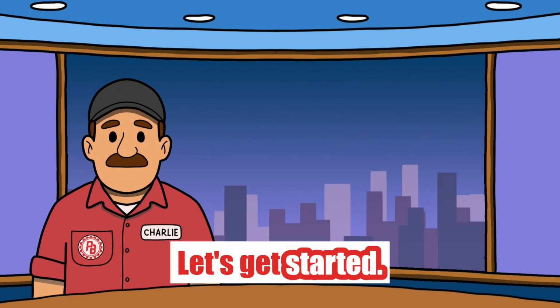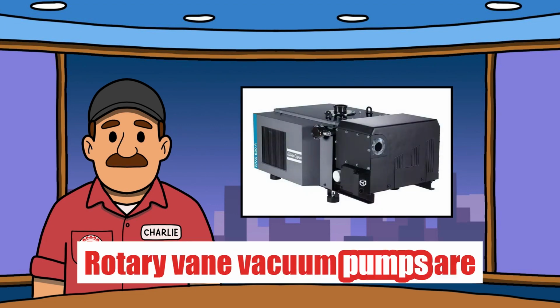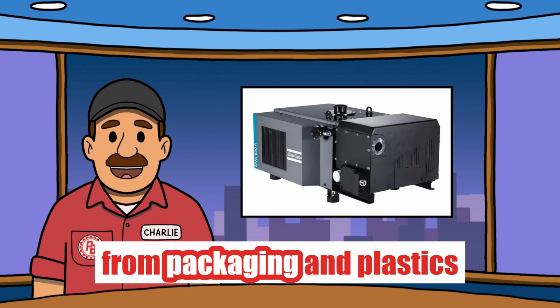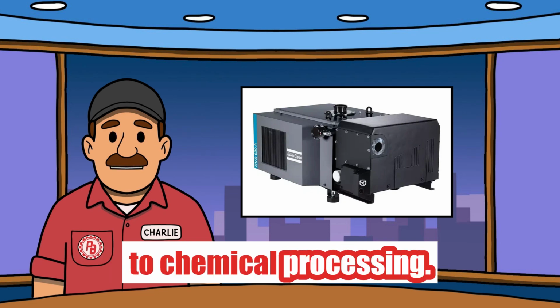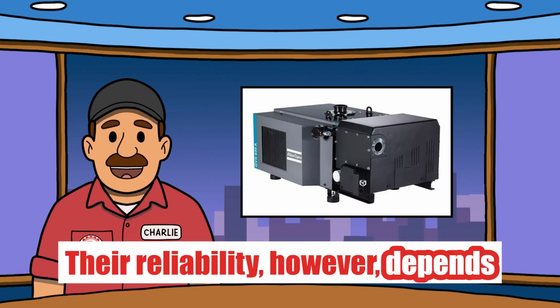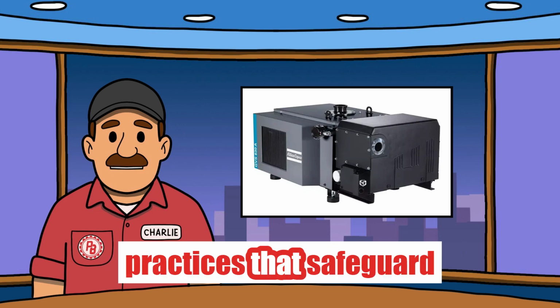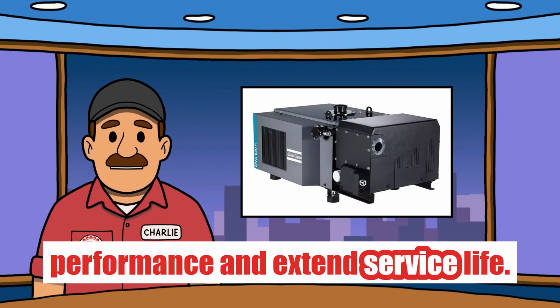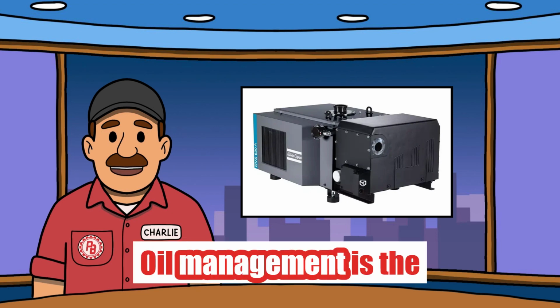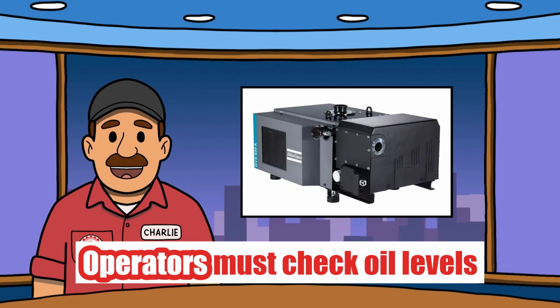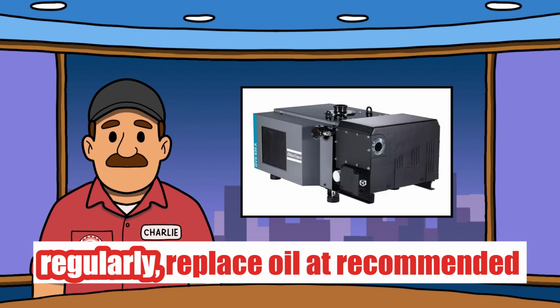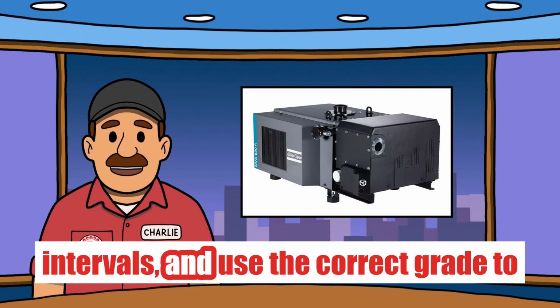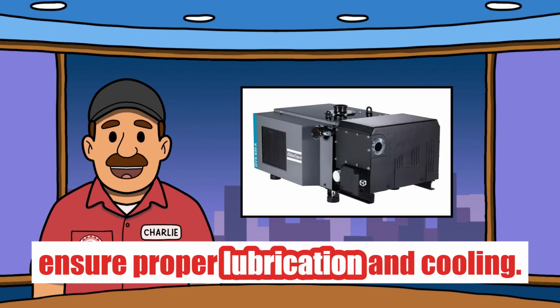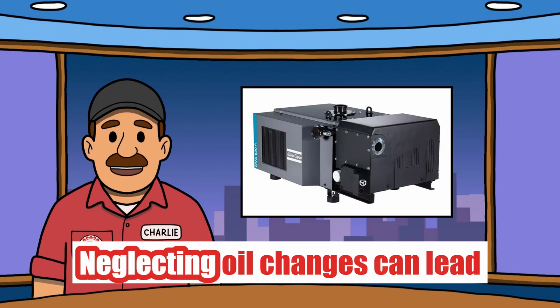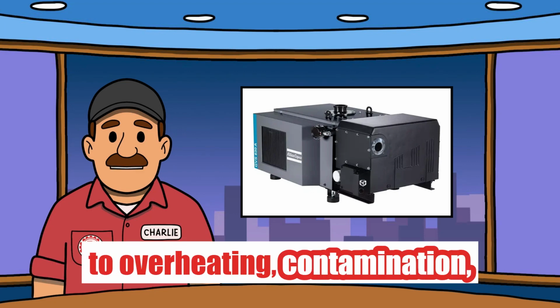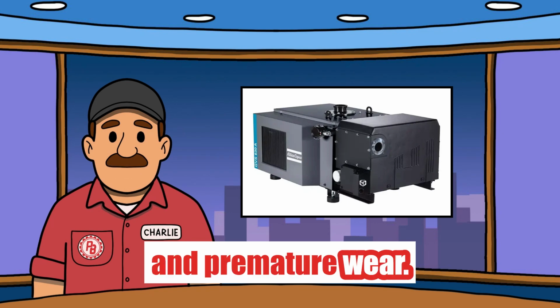Let's get started. Rotary vane vacuum pumps are essential across industries, from packaging and plastics to chemical processing. Their reliability, however, depends on disciplined maintenance practices that safeguard performance and extend service life. Oil management is the foundation of pump care. Operators must check oil levels regularly, replace oil at recommended intervals, and use the correct grade to ensure proper lubrication and cooling. Neglecting oil changes can lead to overheating, contamination, and premature wear.